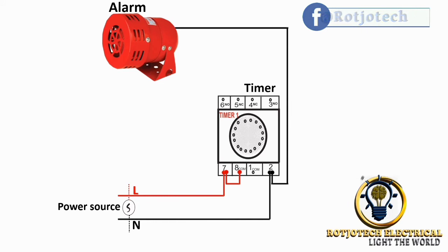After that, the output of this timer. Let me explain this. Terminal number 8 common serves terminal number 5 and terminal number 6, while terminal number 1 common serves terminal number 4 and terminal number 3. Since we have powered terminal number 8 common, or power in, we can only get our output from terminal number 6 or terminal number 5, normally closed.